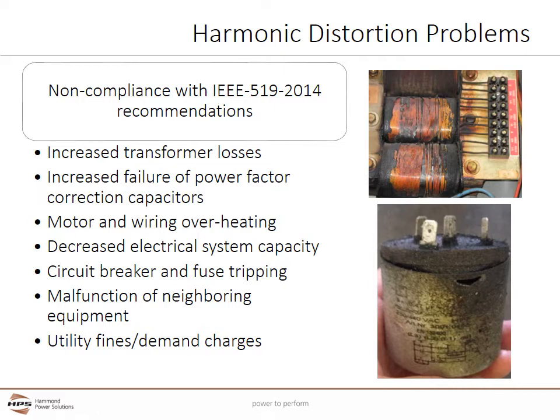The rectification of AC to DC power causes harmonics. Harmonics can cause a number of issues including increased transformer losses, increased failure of electrical power factor correction capacitors — which attract harmonic currents that can damage and destroy them — motors running less efficiently, and wiring and cabling overheating from the additional harmonic currents. This leads to decreased electrical system capacity. Harmonic currents can also cause circuit breaker and fuse tripping, and malfunctioning of neighboring equipment such as communication errors or increased DC power supply failures.